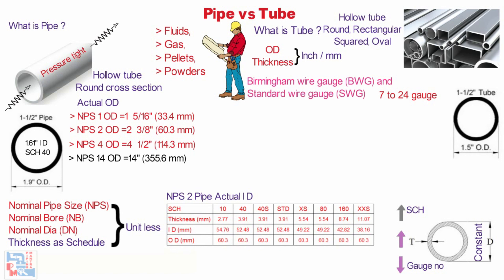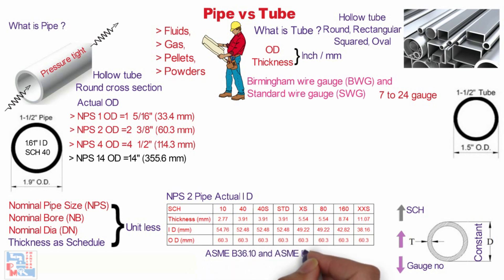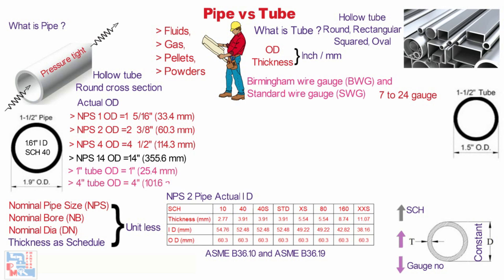The standard combinations of nominal pipe size and wall thickness (schedule) are covered by ASME B36.10 and ASME B36.19 specifications, for carbon and alloy pipes and stainless steel pipes respectively. In the case of tube, the actual OD is the same as the OD mentioned — like a 1 inch tube has an actual OD of 1 inch, and a 4 inch tube has an actual OD of 4 inches.